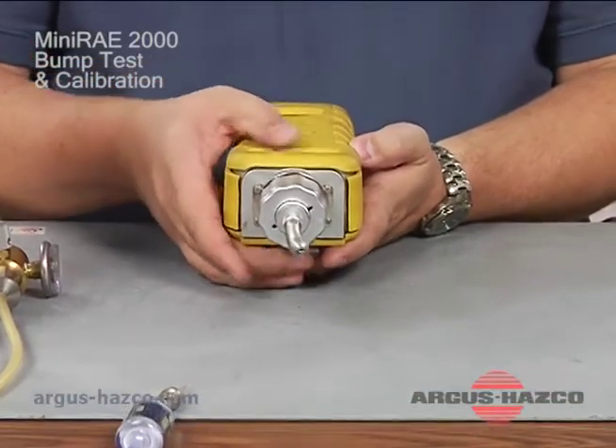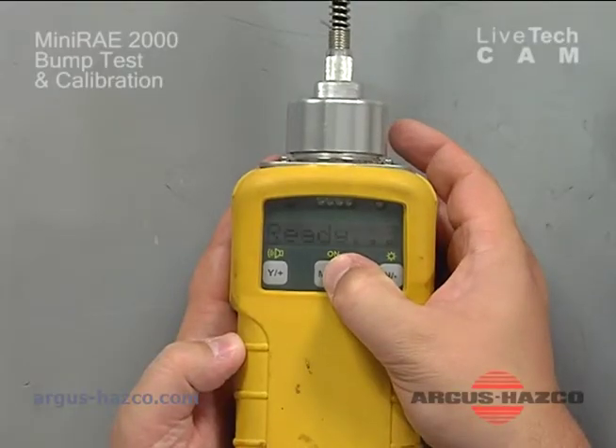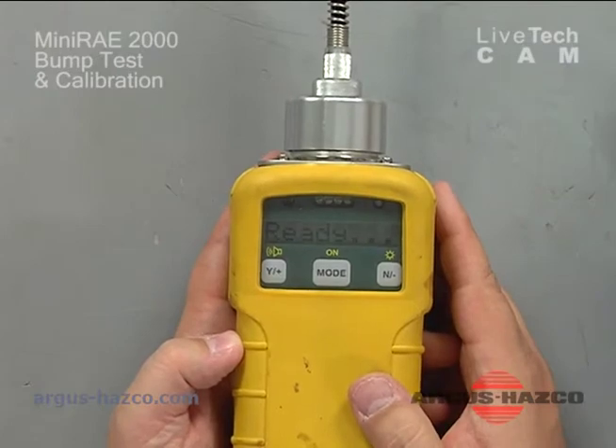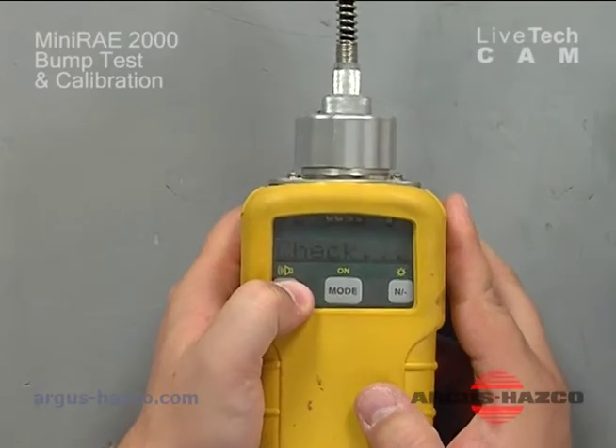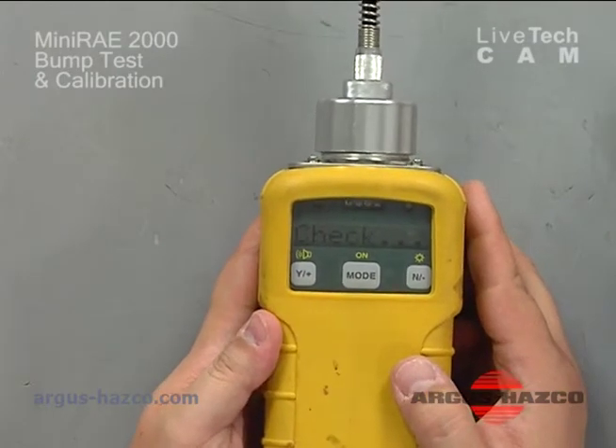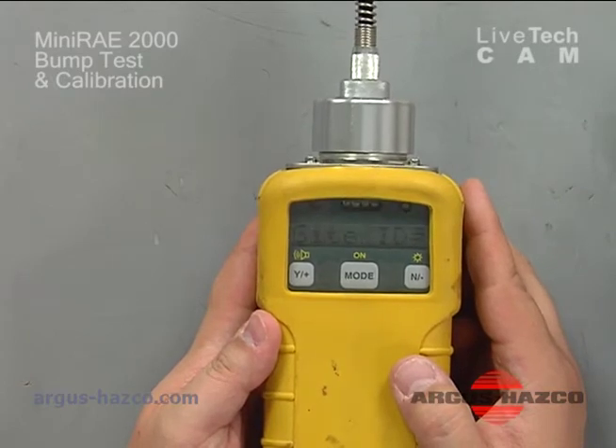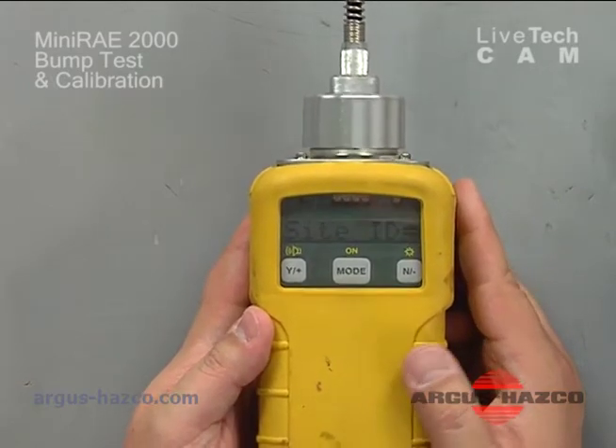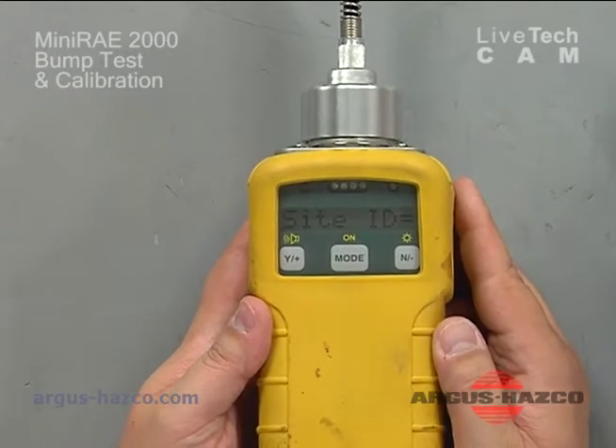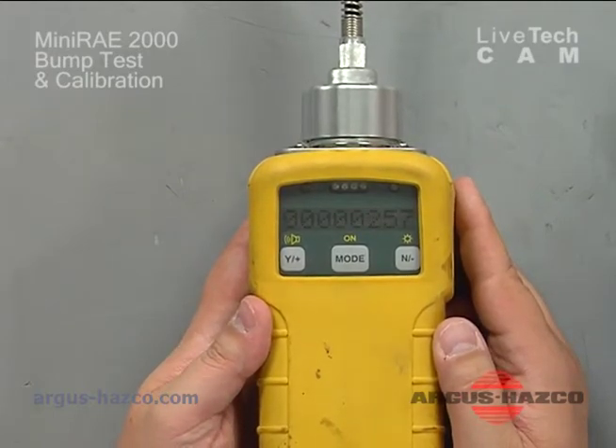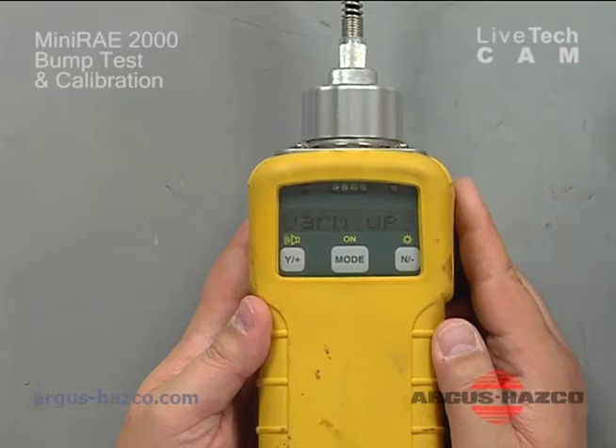If you hit your mode button, it'll go back to ready. You can hit yes. It's going to check. It's going to give you a site ID if you've assigned a site ID to this. It's going to say the gas is equal to isobutylene. It's going to warm up, and it's going to start giving you a reading.